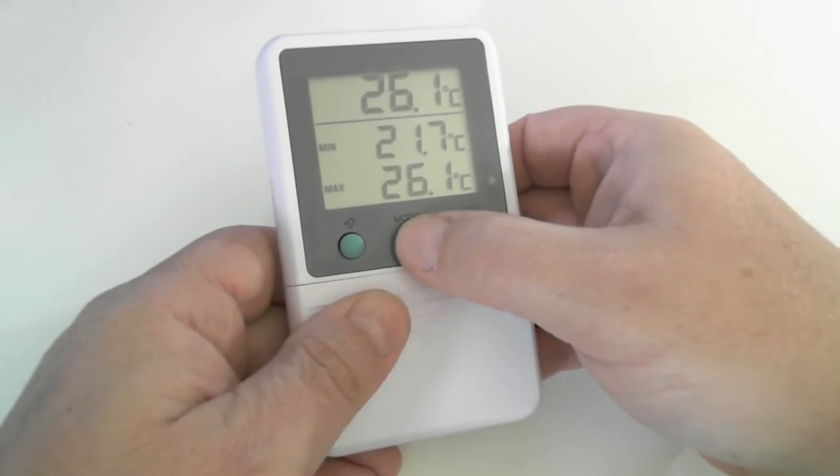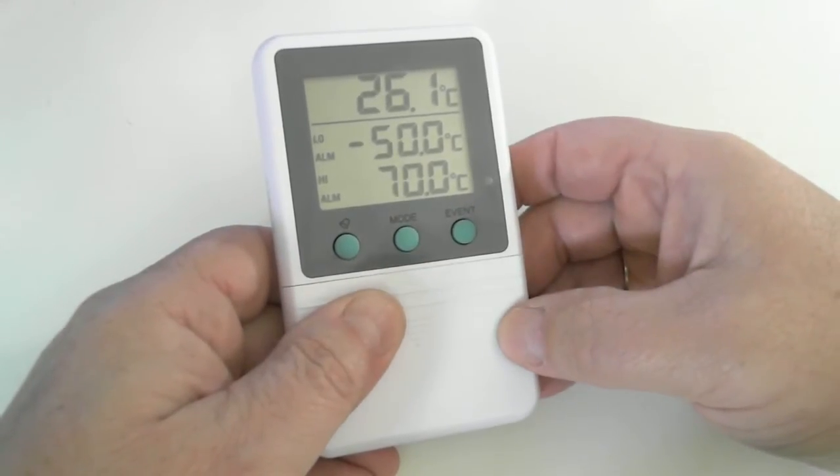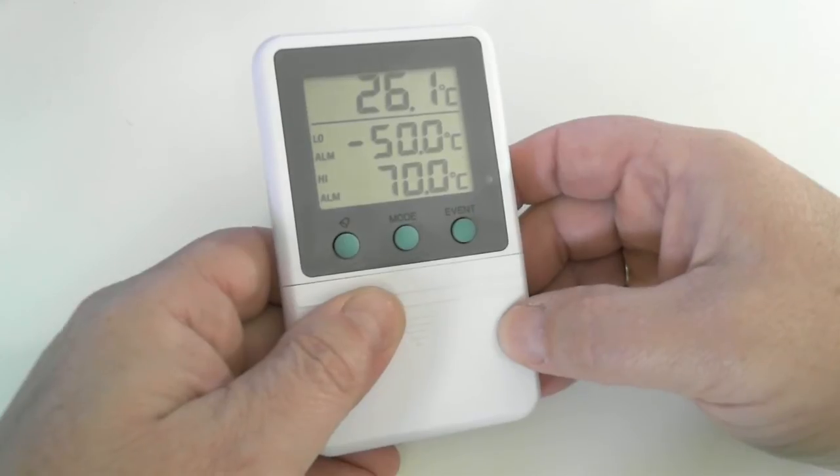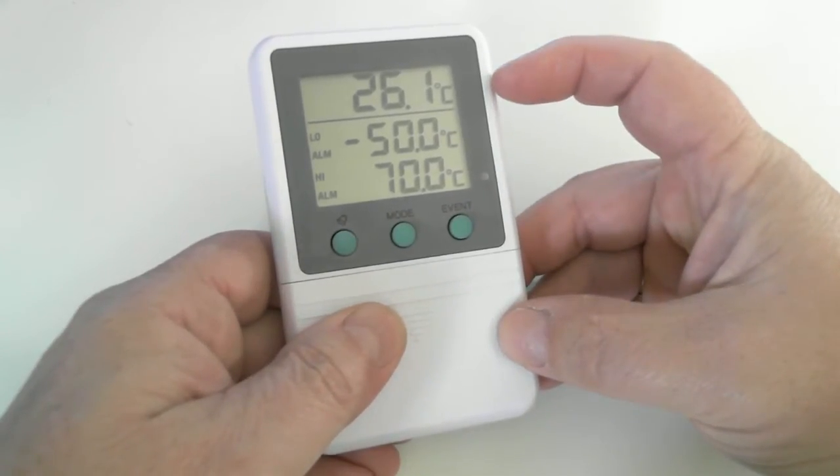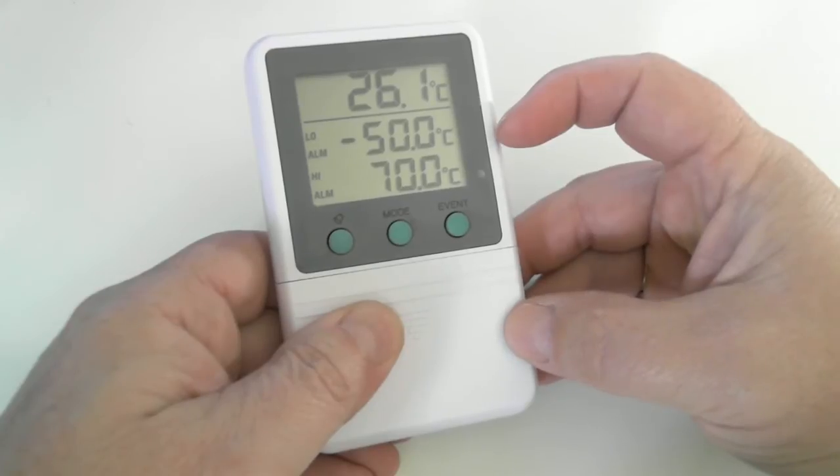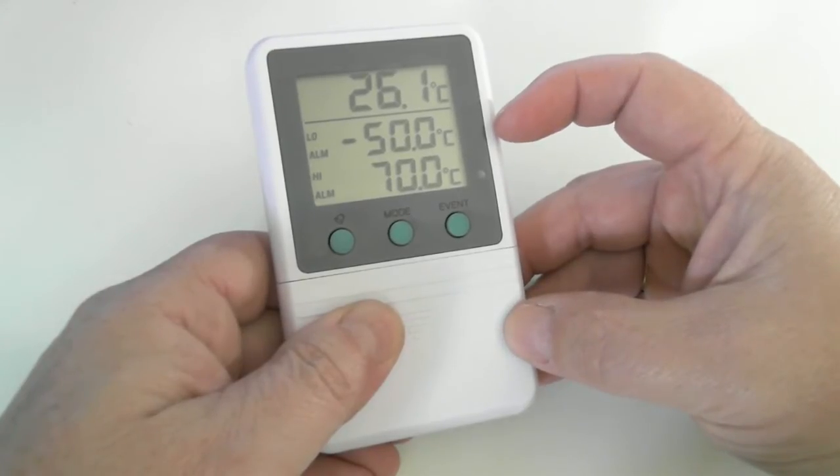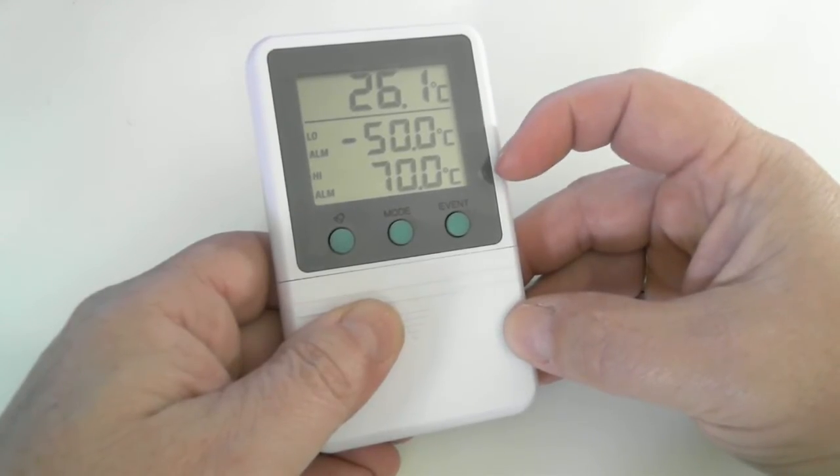Press the mode button and we're now in the alarm display. It's currently showing the current temperature at the top, the low alarm set point, and at the bottom is the high alarm set point.